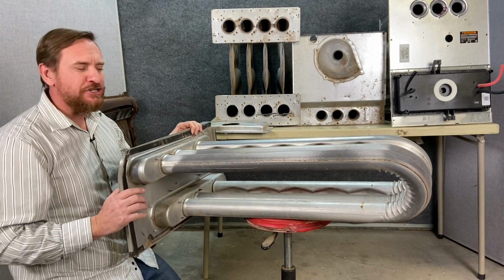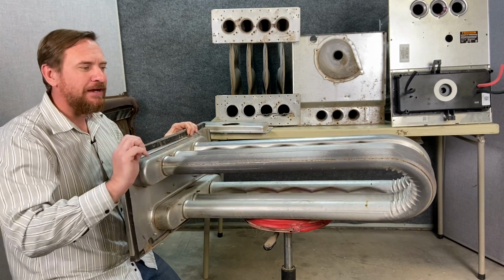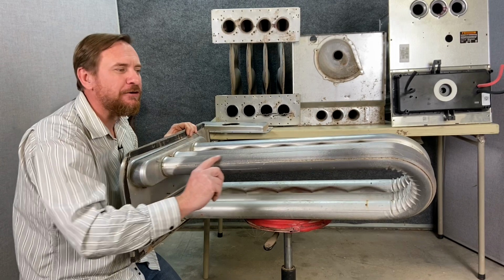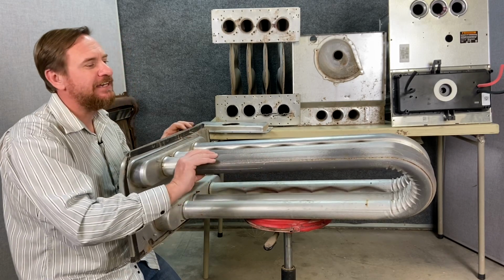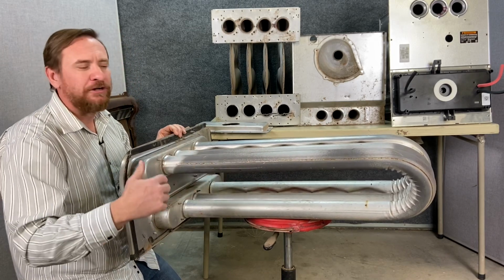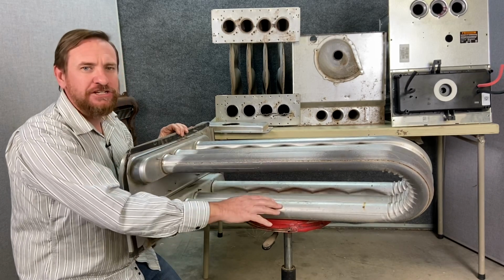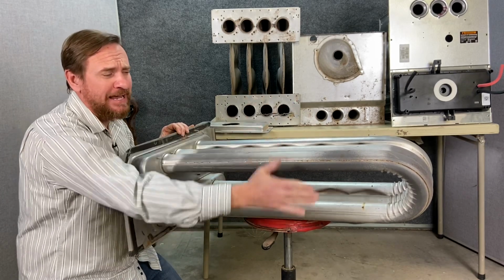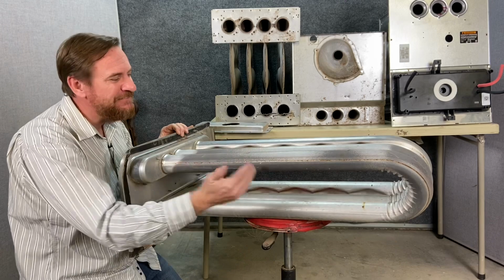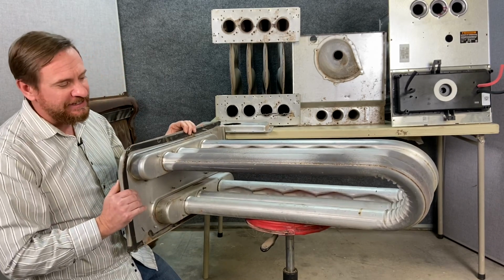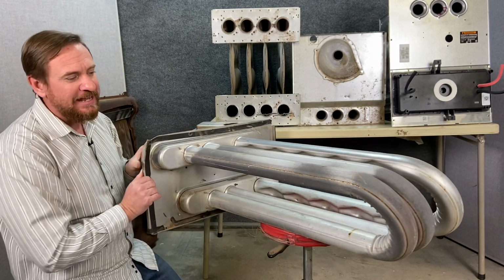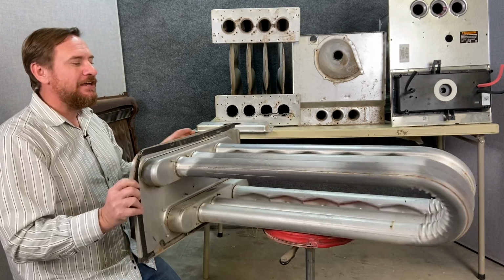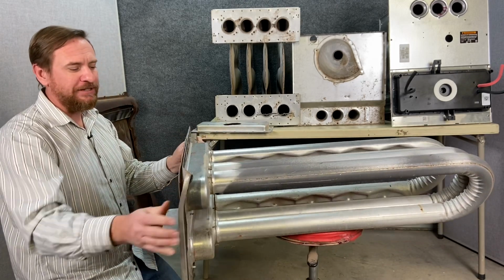So there's a few ways you can check this. You could put a camera, an endoscope, and run an endoscope inside of here at the light and check it from the inside. The other thing is we can look at these heat exchangers, and on package units, they usually had a panel right here. We could take that panel out and physically look at this and see it. This heat exchanger was completely dead, had holes in it, and definitely it was a good thing that this was replaced and pulled out of service.